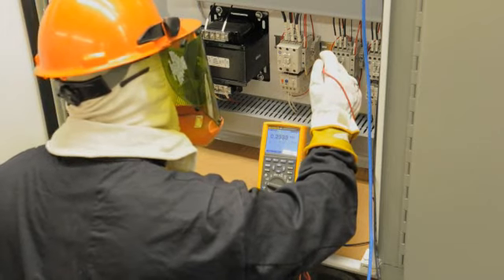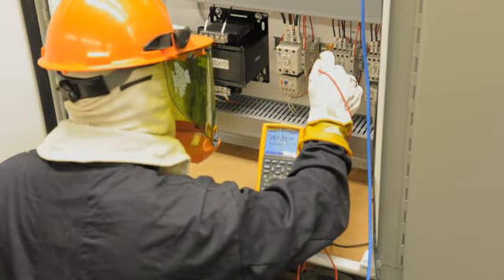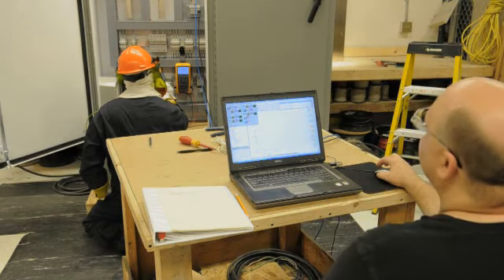On the control cabinet side, they use a Fluke 289 DMM to check the control system's I/O and motor starter relays using the computer interface to trigger each node.